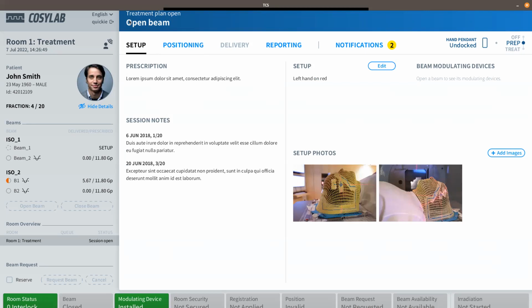The TCS also guides user through the workflow. Here are some instructions, high-level instructions, what to do next. Here are various statuses, which conditions that are required to the process are satisfied, which not. We have some patient information here and also a list of beams. So the treatment session is usually split into several beams, and each beam is used to deliver, let's say, one isocenter dose to, let's say, one isocenter in the patient or from different angle and so on.